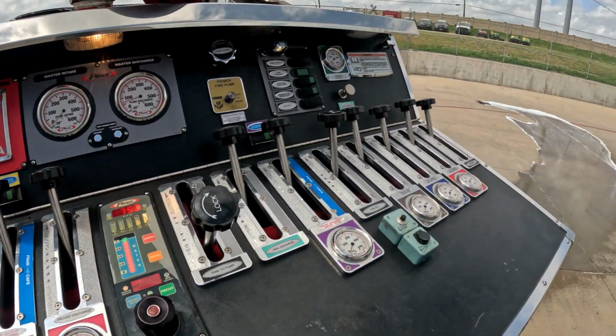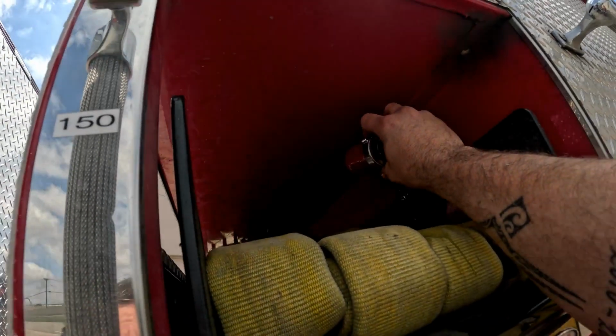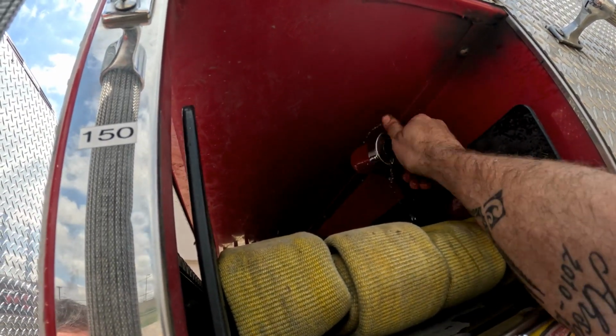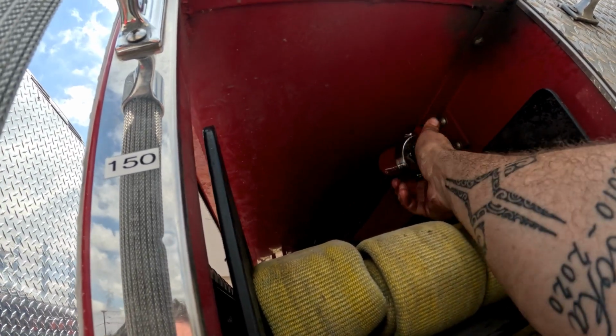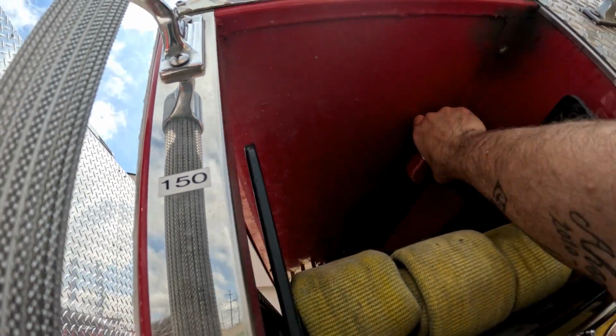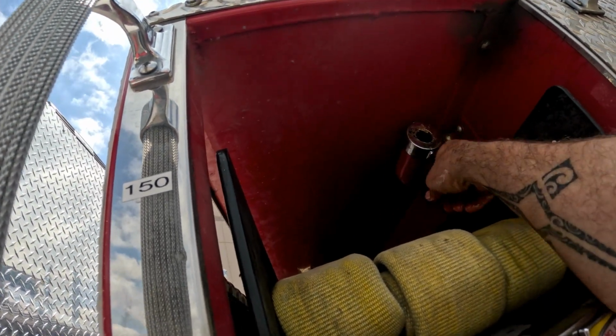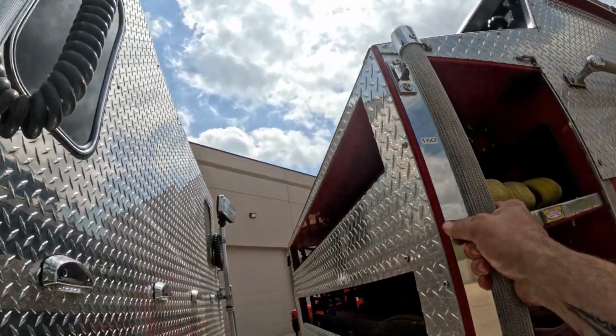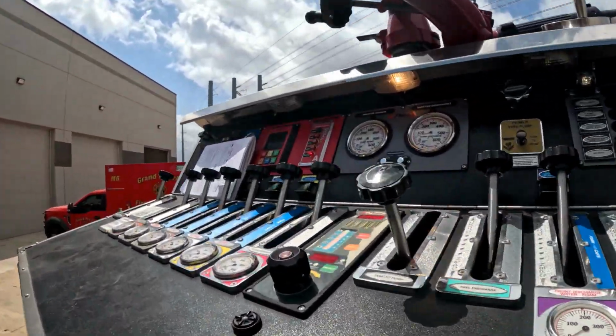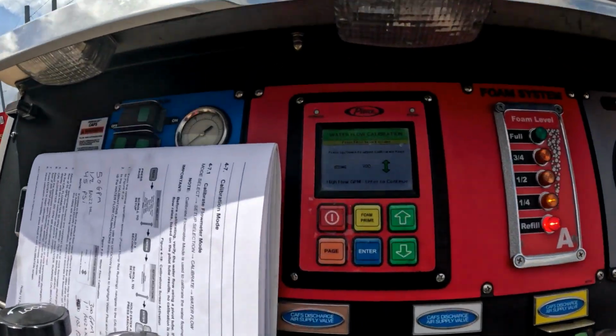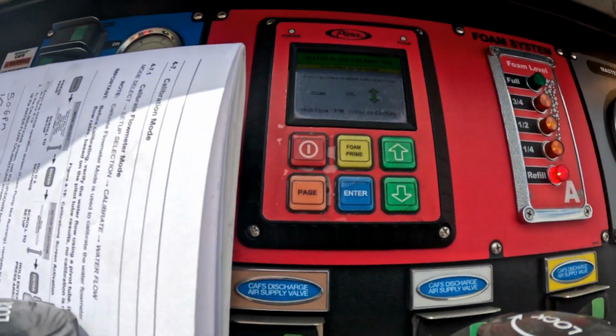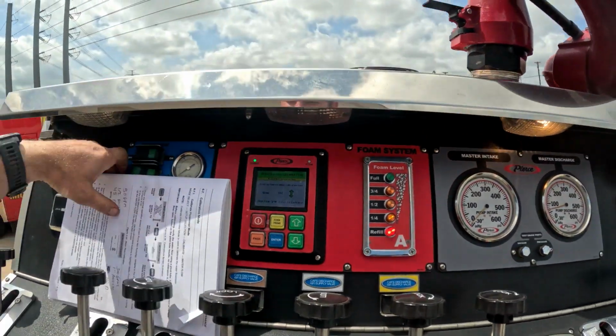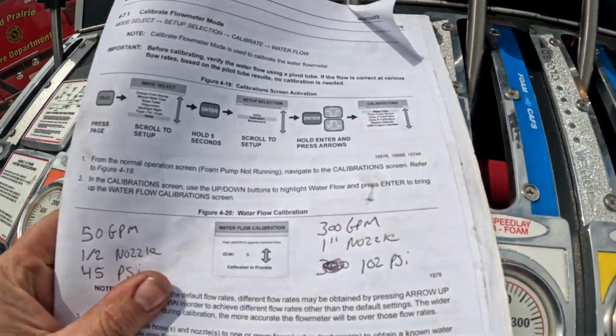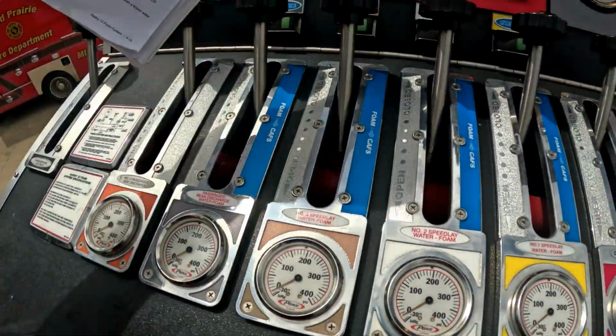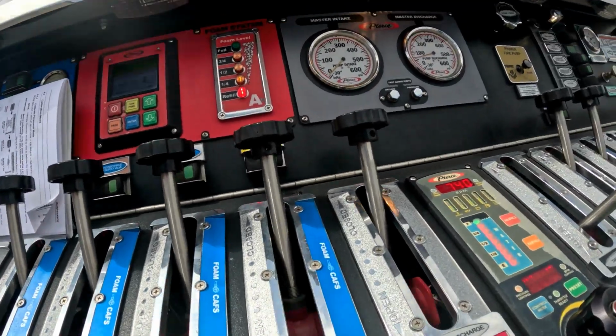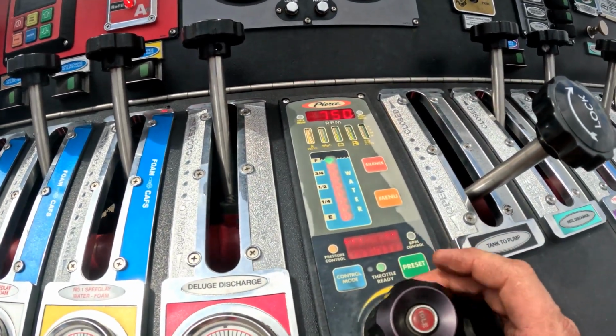All right, so let's go put the 300 cap on. 300 cap, 1-inch hole. I'm gonna have a little bit more pressure, so I'm gonna try to aim this up a little higher. All right, same as before. So it's wanting us to hit enter to continue. And what did we say? 300 gallons per minute on 1-inch line needs to be at 102 PSI. We're gonna dial this up to 102 PSI.